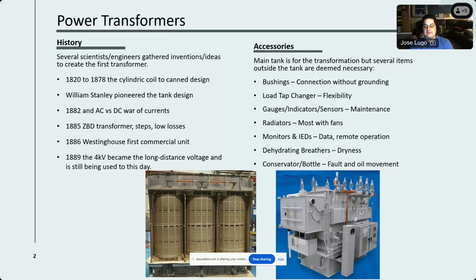And then finally, there are things called a conservator, and a gas bottle, which means basically a tank of gas. And that is to maintain oil movement when there is a fault inside of a transformer, which I'll talk about later in a different slide for quality purposes on a power transformer. So a conservator is basically like another little tank that's connected to the main tank. When there is a fault inside of a transformer filled with oil, the oil will expand. And that conservator will have that space to help the oil move around. It has quite a bit of maintenance on it.